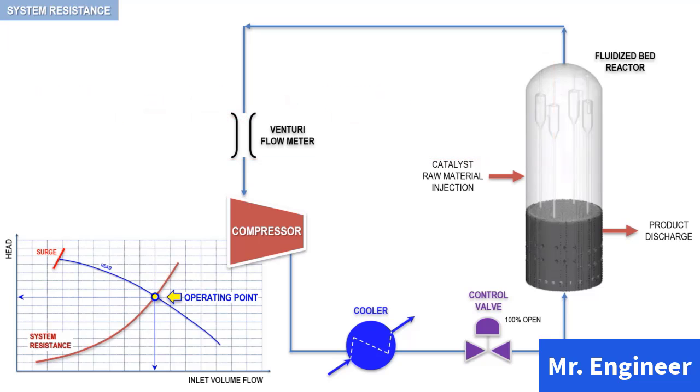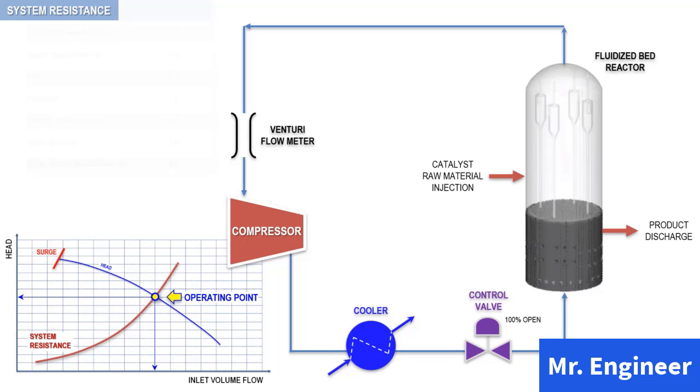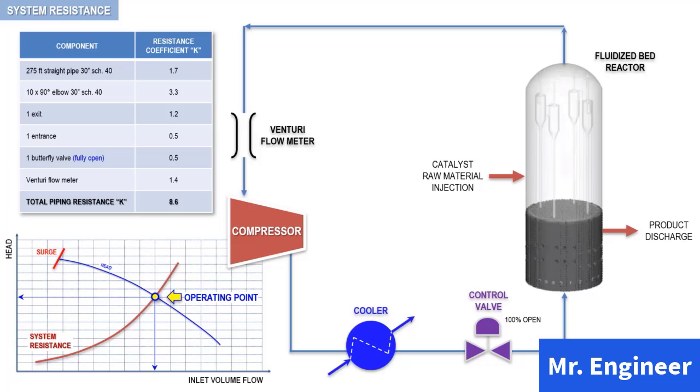Piping losses account for the frictional losses or pressure drops due to pipes, fittings, valves, and instrumentations, such as the venturi flow meter that you can see here. In this table, I have listed all the components making up the piping system with their corresponding resistance coefficient. In this example, the total piping resistance coefficient when the control valve is fully open is 8.6.